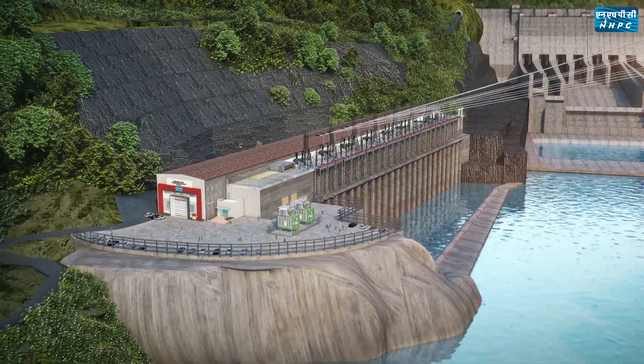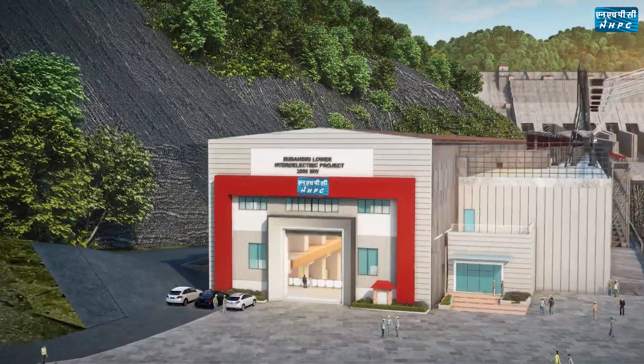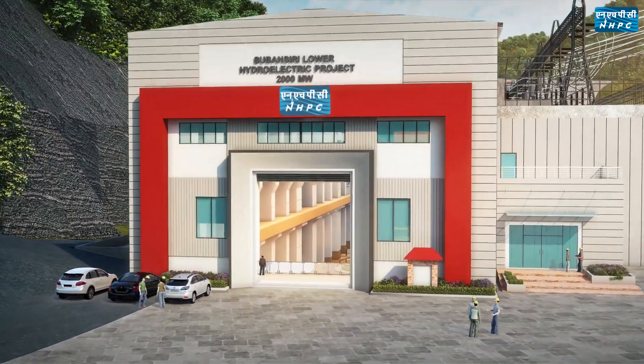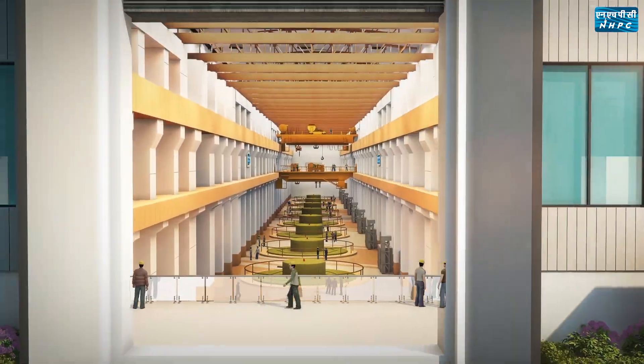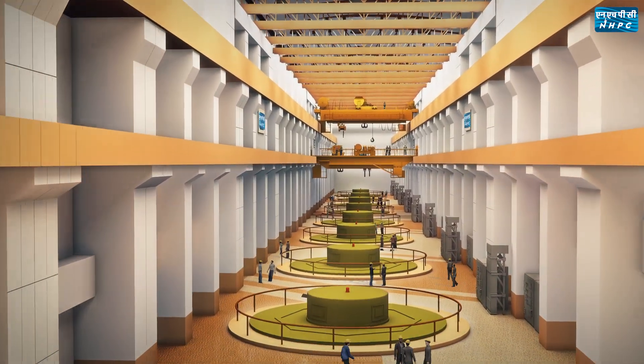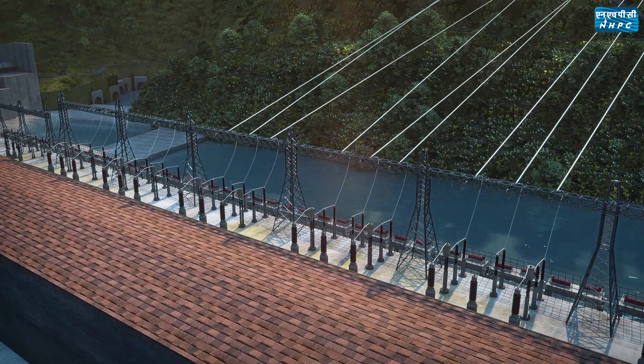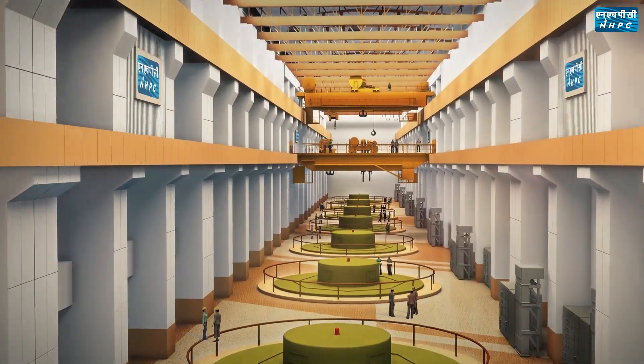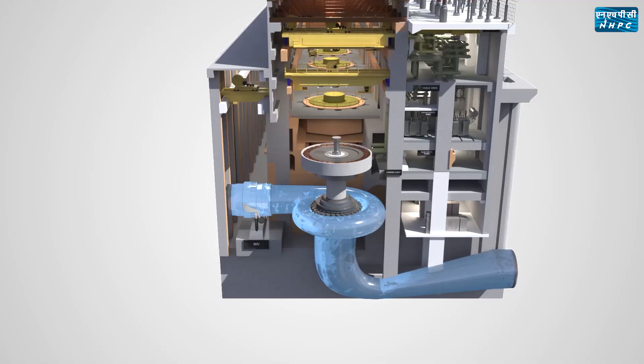The surface powerhouse of Subansiri Lower Project is located on the right bank of river Subansiri. The powerhouse is designed to house eight 250-megawatt machines, transformer bay, GIS block, and pothead yard. The auxiliary building, transformer bay, GIS, and pothead yard are located downstream of the main machine hall. To isolate the machine from the water conductor system, a Main Inlet Valve (MIV) has been provided upstream, just adjacent to the machine hall.